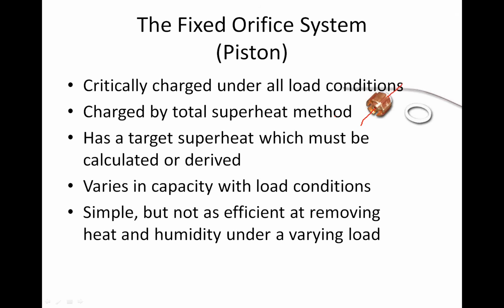It's charged by the total superheat method, which I'm going to review here in the next couple slides. It has a target superheat which must be calculated or derived. Now, again, we usually use that charging chart, but there is a formula to calculate target superheat if you want to do that, and I'd have to dig it out real quick. I always use a chart just because it's more convenient. And it varies with capacity and load conditions.